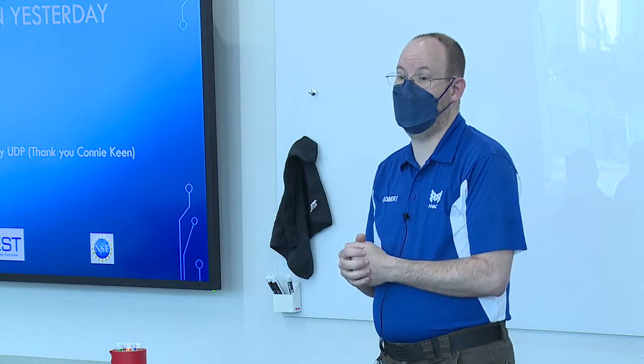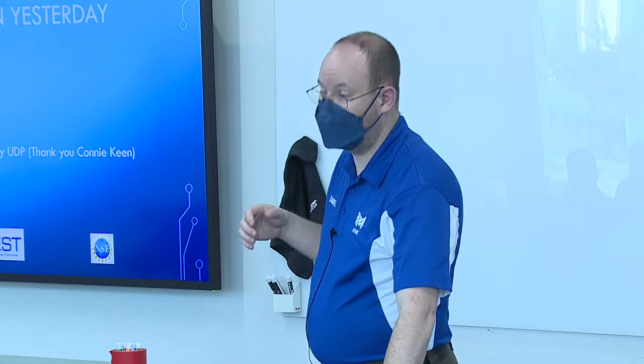BACnet is a standard. It's one of those standards just like you'd expect out of ASHRAE. It started over here on this corner, and then it grew and expanded. So some of where it started influences its legacy moving forward. BACnet was originally designed as an MSTP protocol, a 2-wire communication. Then it grew into an Ethernet protocol, okay? So the literal networking hardware level.